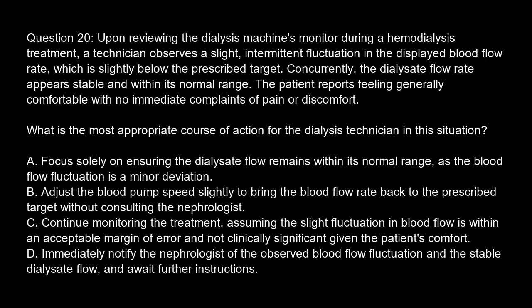Option A. Focus solely on ensuring the dialysate flow remains within its normal range, as the blood flow fluctuation is a minor deviation. Option B. Adjust the blood pump speed slightly to bring the blood flow rate back to the prescribed target without consulting the nephrologist. Option C. Continue monitoring the treatment, assuming the slight fluctuation in blood flow is within an acceptable margin of error and not clinically significant given the patient's comfort. Option D. Immediately notify the nephrologist of the observed blood flow fluctuation and the stable dialysate flow, and await further instructions.